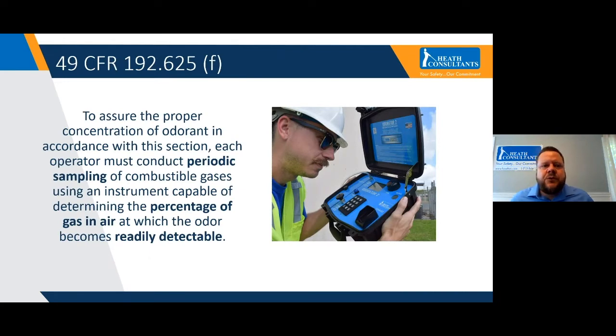So let's dive into 192.625 section F. Now we're getting into the equipment and what equipment is required to detect whether there's enough odorant in a system. So what this regulation states is that an operator must conduct a periodic sampling of the gas with an instrument capable of determining percent of gas in air at the level of readily detectable. And so this is where a device like the Odorator 2 comes into play.